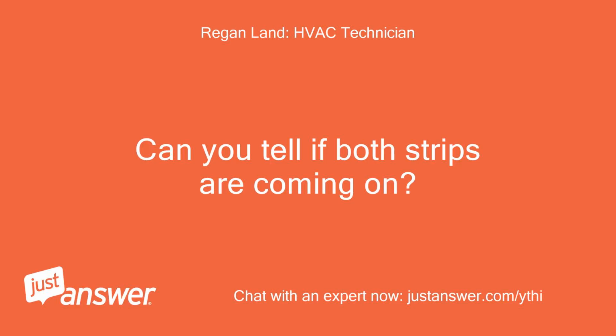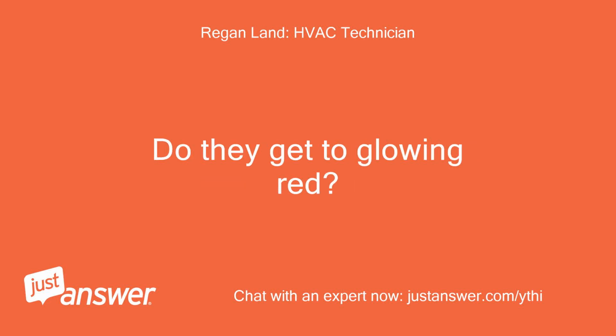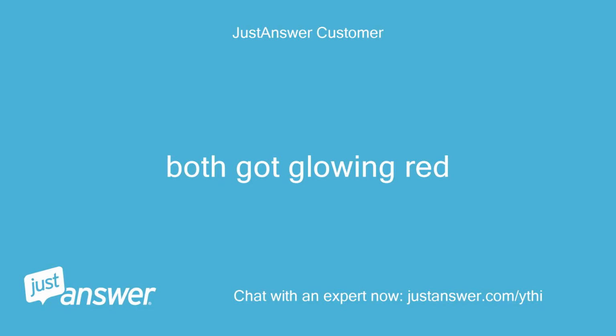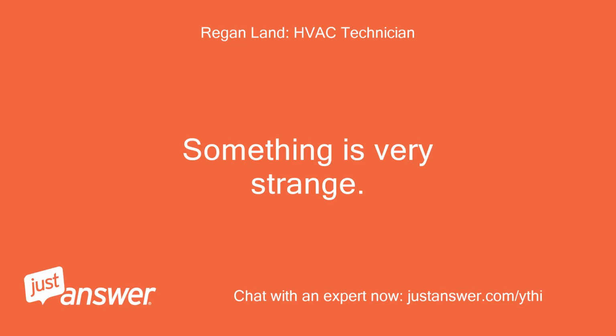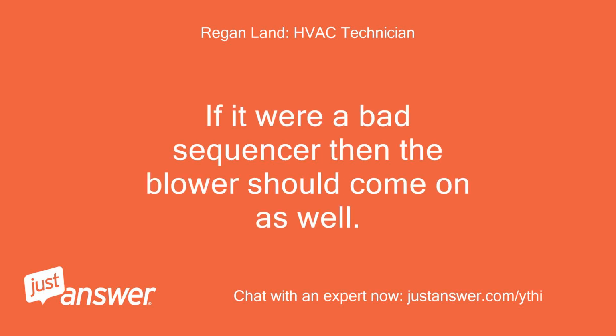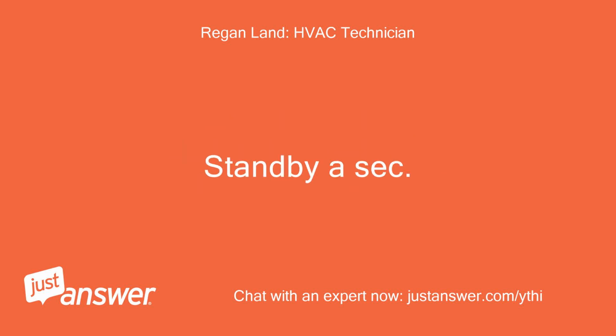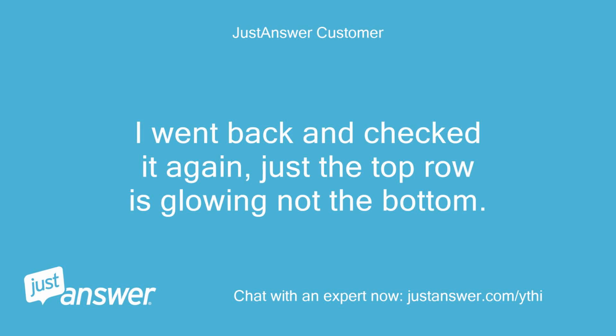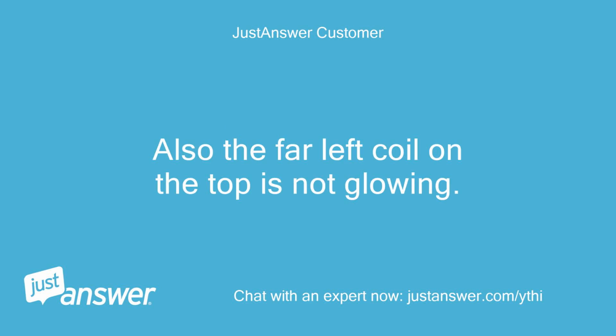Can you tell if both strips are coming on? Do they get to glowing red? Both got glowing red. Something is very strange. If it were a bad sequencer then the blower should come on as well. Stand by a second. I went back and checked it again, just the top row is glowing, not the bottom. Also the far left coil on the top is not glowing.